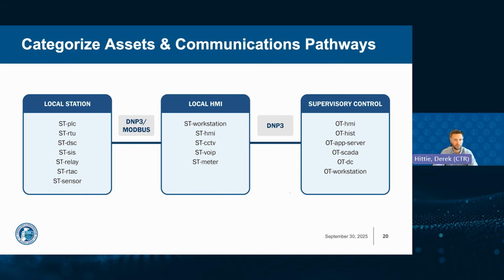Zone 2 then is the local HMI or station level interface, where you'll find your engineering workstations and HMIs, maybe CCTV or VoIP phones, and meters. These provide operators and technicians with visibility and local control over the process, but they do not directly trip or actuate equipment. And then zone 3 is our supervisory control. This layer includes your SCADA servers or application servers, your historians, maybe domain controllers and HMIs, and maybe some operator workstations. This is where supervisory functions happen, shifting focus to the broader situational awareness, your logging and reporting, and remote control.